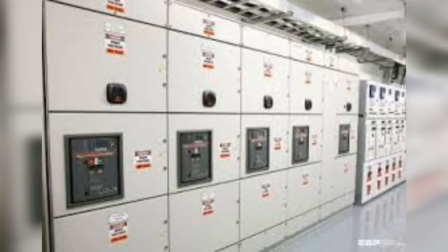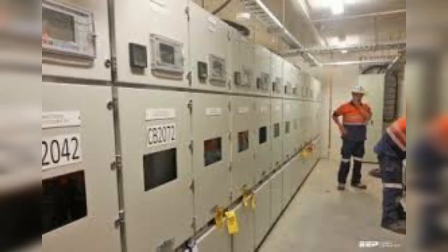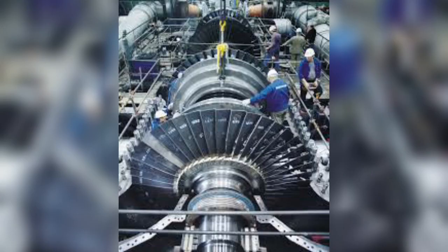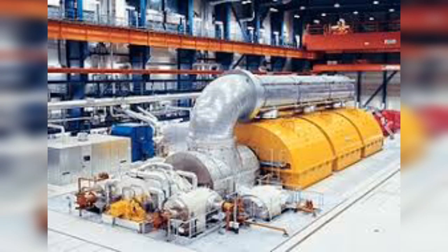What are surge protection devices? Electrical equipment in a distribution system may be exposed to internal or external surges. Internal surges are generated within the facility by user equipment. They result from a switching process, for example, switching a capacitive load, or a fuse or breaker opening in inductive circuits.